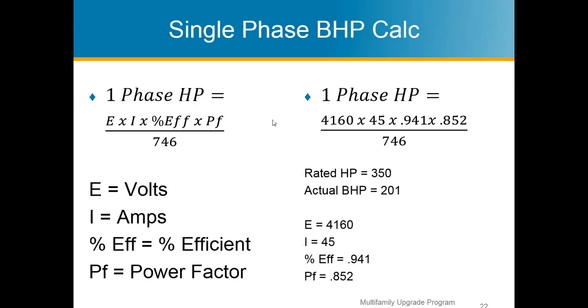So again, here's just the things you need to know to get a brake horsepower. This was a slide from the last presentation I did. It's a one-phase horsepower. You need to know the volts, amps, percent efficiency, and the power factor. So this is just that calculation over again. 746 is your watts to horsepower. Since volts times amps equals watts, we're dealing with watts here, and then we want to end up with horsepower. So for a motor with a rated horsepower of 350, the actual operating condition of that motor would be 201. Obviously you're not going to have that as your indoor unit on these things, but the math is basically what I'm trying to show here.